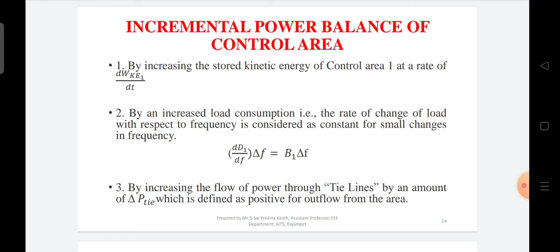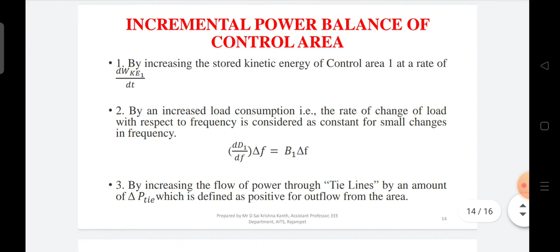One is the increase in stored kinetic energy, represented as dWke1 by dt. Due to increase in load consumption, it is represented as dD1 by dF into delta F, that is B1 delta F. Similarly, the third one, increased flow of power through tie lines, is represented as delta P tie. So it is finally represented as delta PG1 minus delta PD1 equals dWke1 by dt plus B1 delta F plus delta P tie. This is for an interconnected system, that is, control area 1 must be connected at least with control area 2, and so on up to control area n.